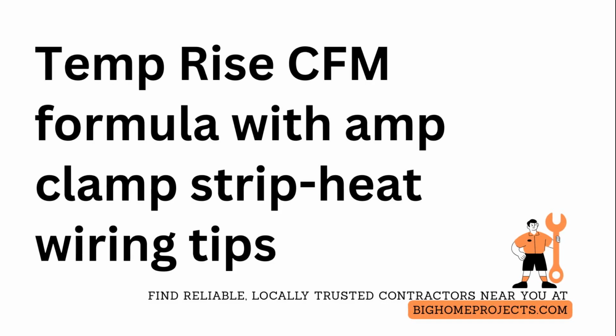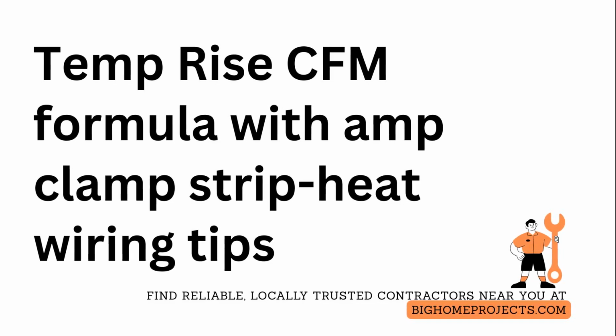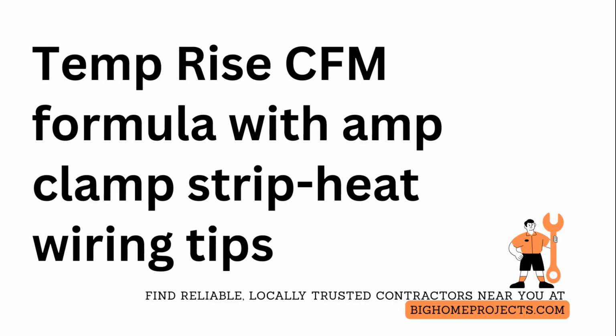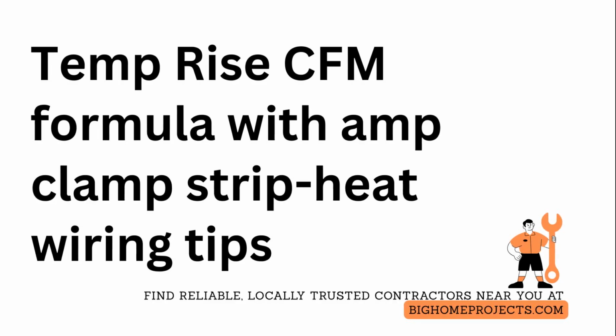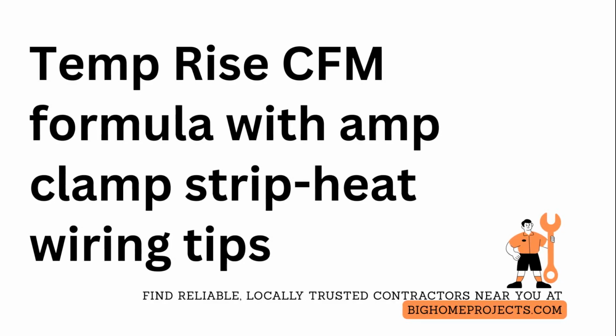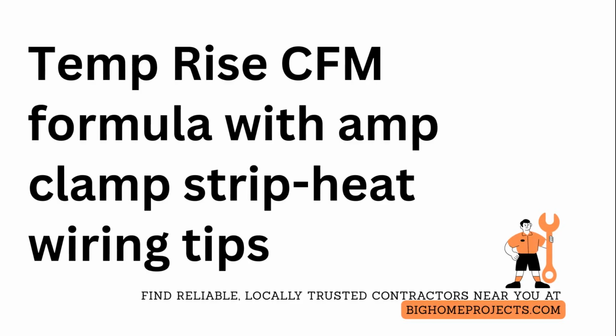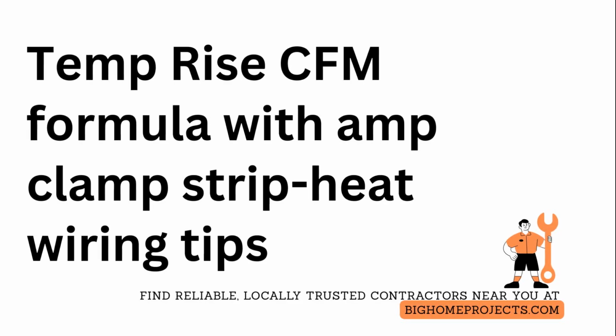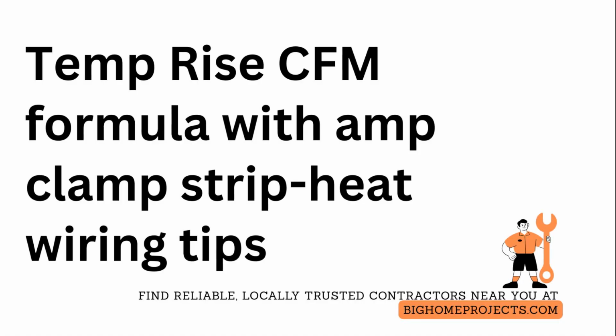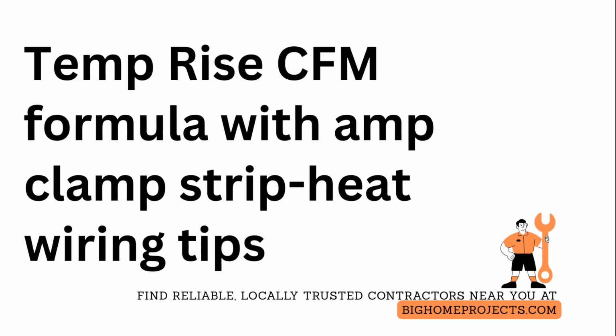Measure airflow cubic feet per minute quickly and accurately with the heating, ventilation, and air conditioning temperature rise formula by using supply minus return temperature and heater wattage, while safely setting your amp clamp to read only the electric strip heat leg so you do not cook the numbers or yourself.